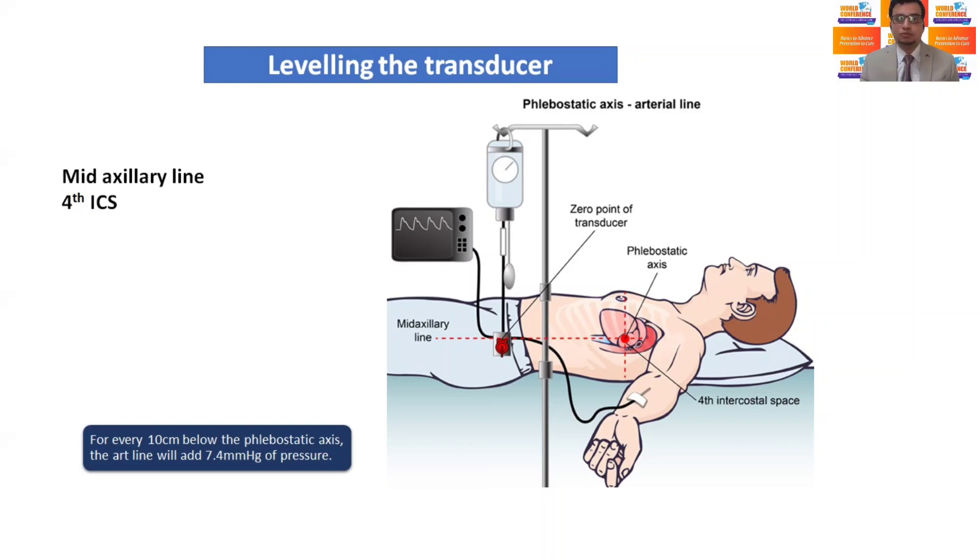The transducer should be leveled using the clamps along the phlebostatic axis, which is the junction of the fourth intercostal space and mid-axillary line. For every 10 cm below the phlebostatic axis, the arterial line will add 7.4 mmHg of pressure, hence overestimates it.